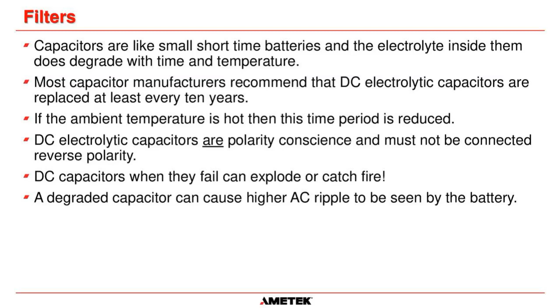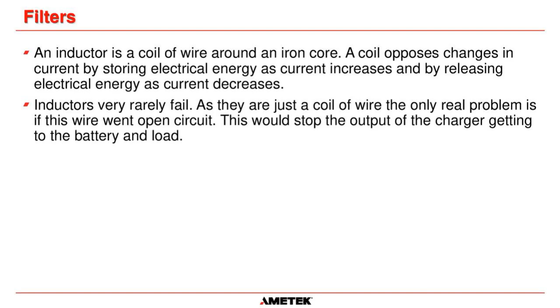Also, a degraded capacitor can cause higher AC ripple to be seen by the battery. Now, an inductor is just a coil of wire wrapped around an iron core. The coil opposes a change in current by storing electrical energy as current increases, and by releasing electrical energy as current decreases. It's kind of like a transformer without a secondary. Inductors very, very rarely fail because they're just a coil of wire. The only problem usually is if that wire went open circuit, which would stop the output of the charger getting to the battery and to the load circuits. But it's very, very rare for that to happen - inductors very rarely fail.